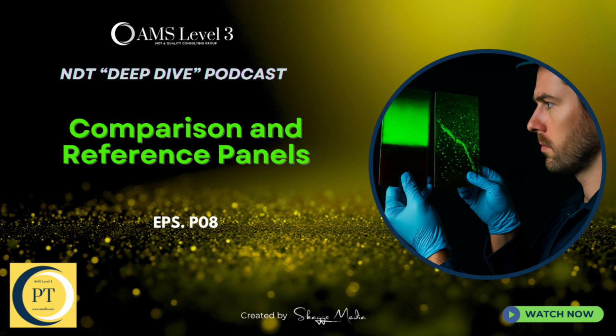And the source really hammers home that this panel's value depends entirely on the technician looking at it. 100%. This is where the trained eye is irreplaceable. The panel might still show the cracks, right, but maybe the indications look dimmer or fuzzier than usual. Perhaps the developer isn't pulling penetrant well or the wash left too much background. The experienced technician needs to see that and recognize, hold on, this isn't right, compared to how it looked yesterday or compared to a reference photo.